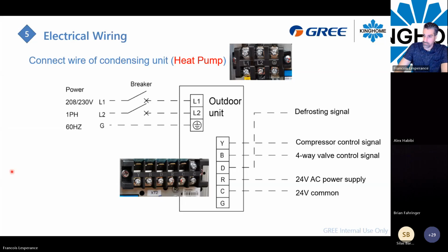So, I just made this wiring right here. I had some pictures of what it looks like in real time. You will see the G here. There are only 2 screws, but nothing to do with it. And so you will have, as I said, your compressor signal, reversing valve, your defrost signal, the R for the power, and the common right here.